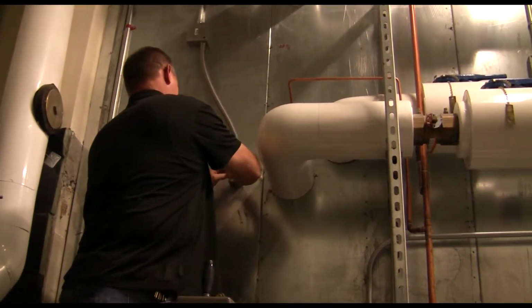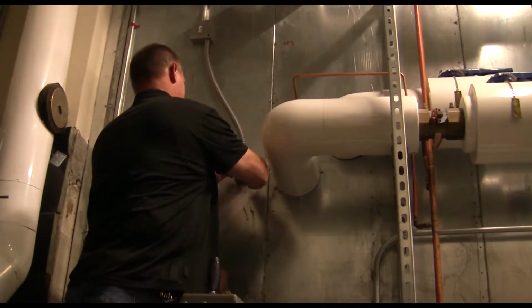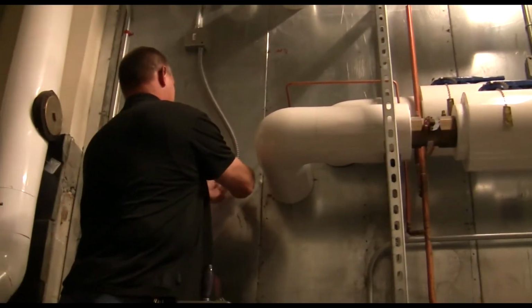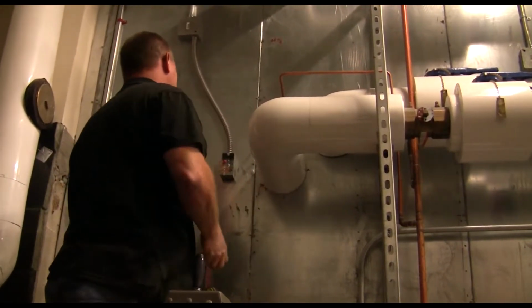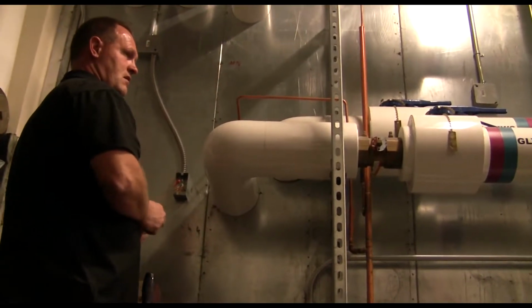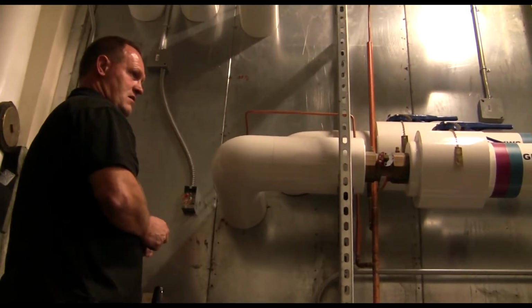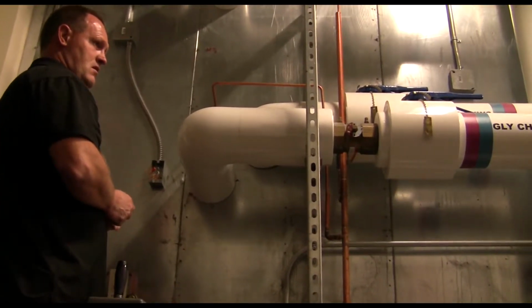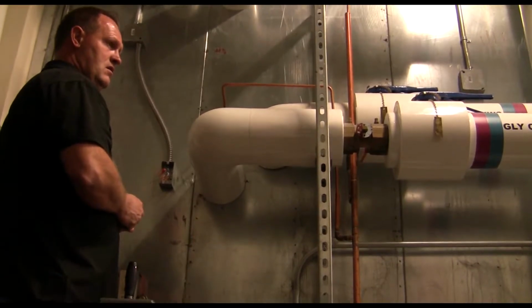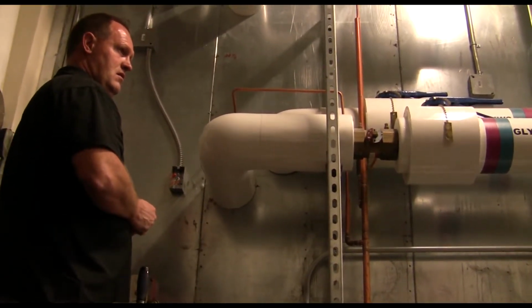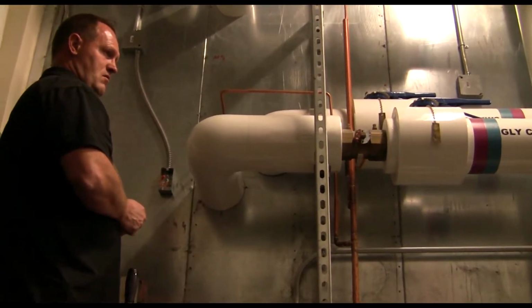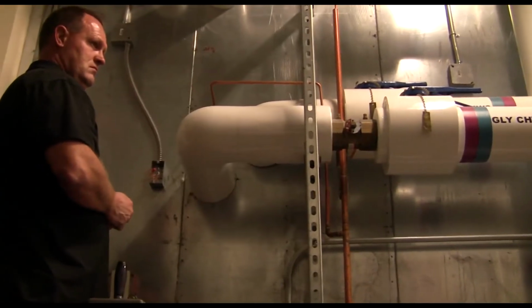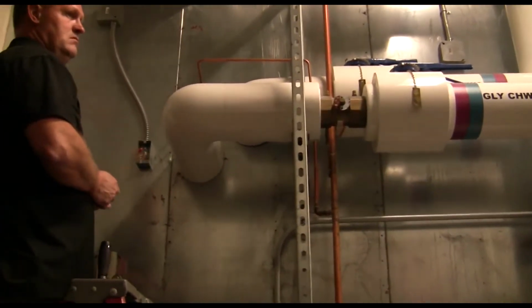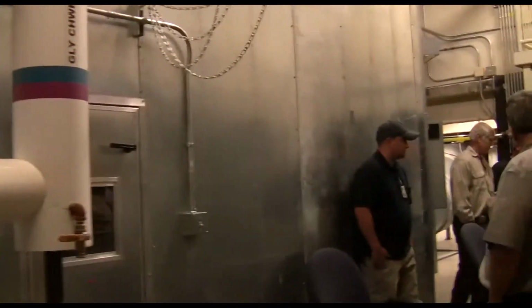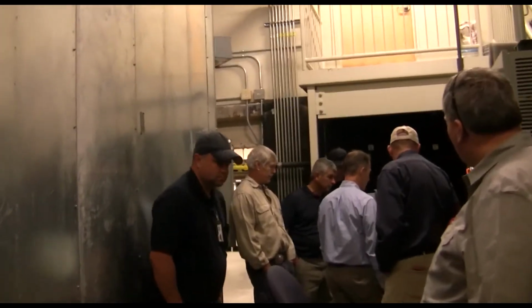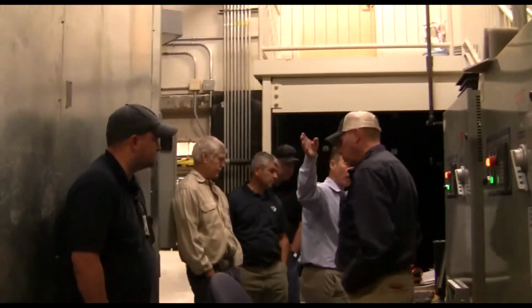And Brooke, what do you see? Nothing yet. Just still. What is that scraping? Okay, what do you got? Okay, so that's the one, that's the discharge. So which discharge? Just right after the control. So it went to NAN, well, minus 140. If I mouse over it, it shows me which sensor it's tied to. So it's the heating coil discharge temp that's mounted right there.